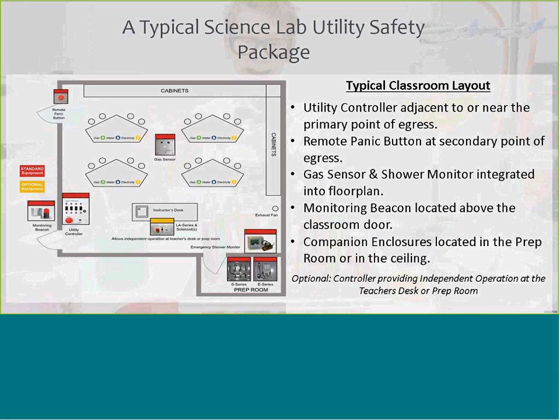The electrical panel doesn't necessarily have to be in a classroom, but usually you want to locate it within the classroom, let's say above the ceiling, between the main panel you design to and the receptacle. You don't want to shunt that electrical panel off. You want to control it with a mechanically held contactor that you can latch and unlatch as the day goes on.